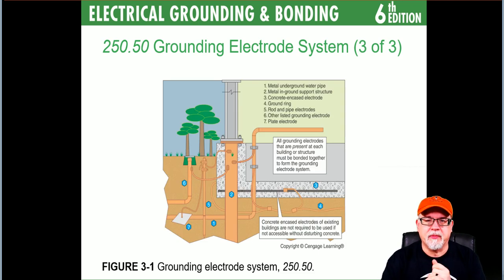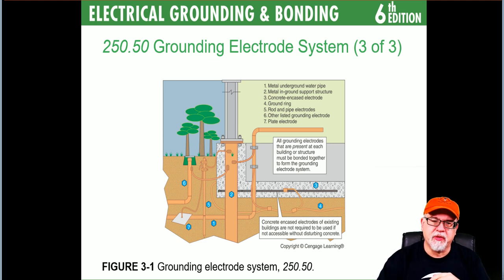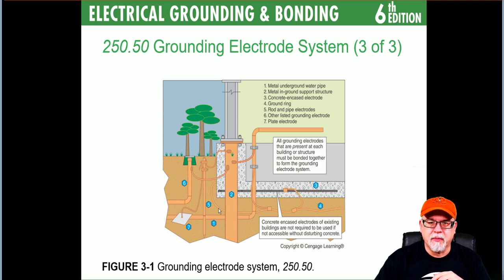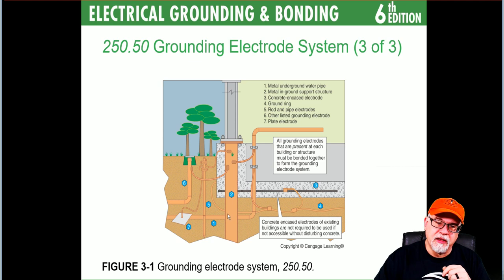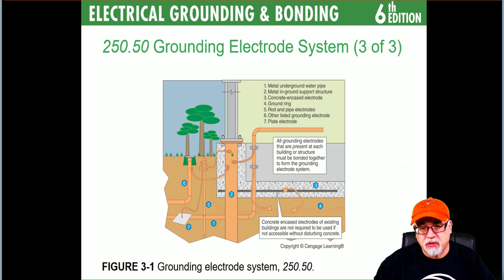Looking at the types A1 through A7 on screen: number one is the metal underground water pipe — 10 feet in contact with the earth. Number two is the in-ground support structure, which can be concrete encased or directly driven into the ground — basically the metal frame of the building driven down into the ground.